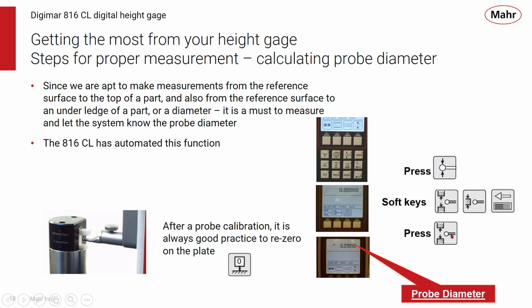You choose the one you want, and then you press that one, and it'll automatically move to the bottom of the ledge and the top of the ledge, and it's going to calculate the probe diameter for you. So it's a very easy to use automated system for calculating the probe diameter. And again, you should probably do that a couple of times a day just to ensure that it's a clean probe and you're ready to make good measurements. It's a way of helping improve the steps to get the proper measurement.